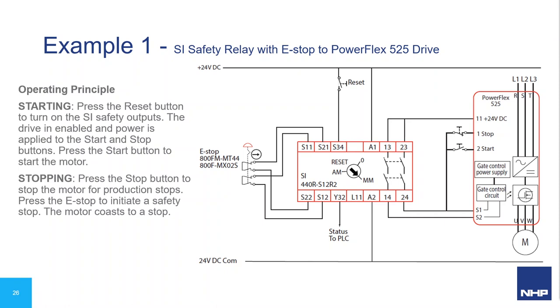Now some examples of how these products are connected together. In the first example, an emergency stop operator with two self-monitoring normally closed contact blocks operating in dual-channel redundancy is monitored by a SI single-input safety monitoring relay. The relay outputs control the power supply to the drive and specifically the gate control circuit performing the safe torque off function. To start: press the reset button to turn on the relay outputs, the drive is enabled, and you can then press the start button. Pressing the e-stop disconnects the gate control circuit and the motor coasts to a stop.